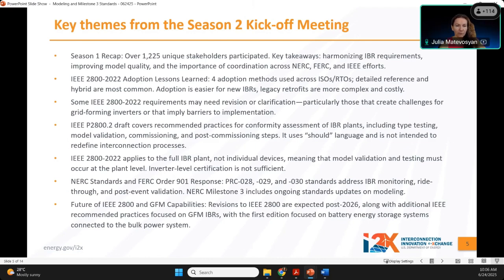It's impossible to achieve because the requirements are at the point of connection. And secondly, it's not sufficient if the inverter-based resource unit is IEEE 2800 compatible—that doesn't necessarily ensure the entire plant is conformant with IEEE 2800.